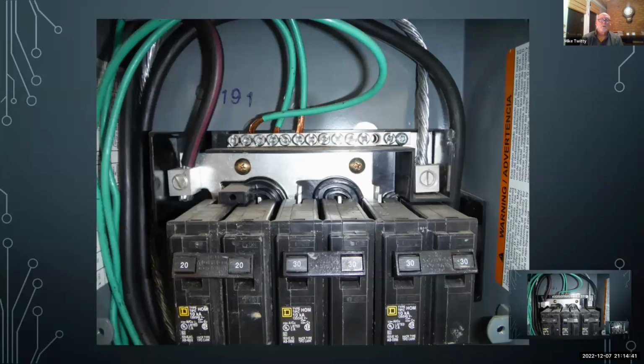Okay, here's a typical little sub panel where you see it's got three 2-pole breakers in. It's feeding some kind of equipment, no 120 volt loads, no neutrals. So it's just got an equipment grounding feeder coming in, but there's something missing here. That's where the bonding screw goes. That's what I was talking about earlier. All metal enclosures must be bonded. There's no neutral even involved in this because this is for air conditioning loads, probably. That's what I'm assuming.